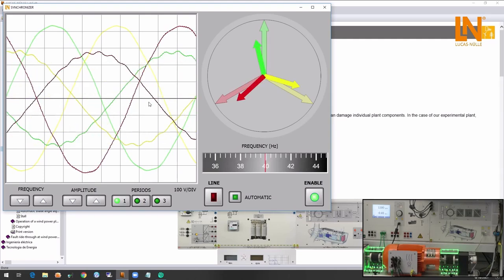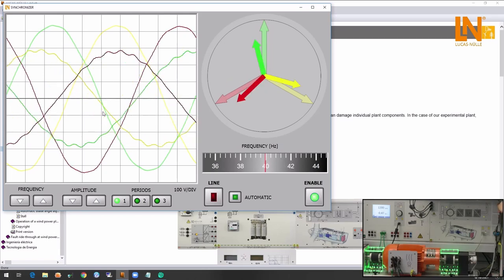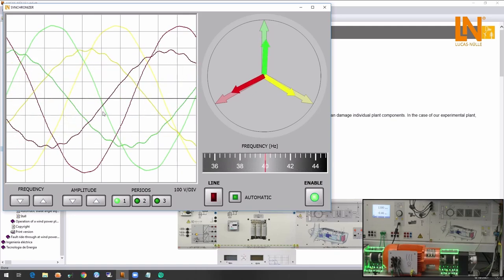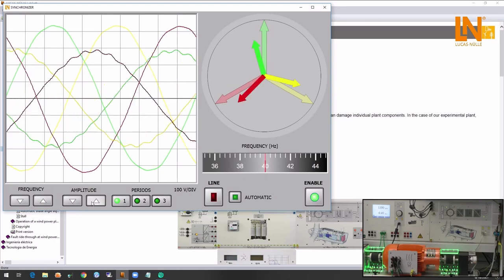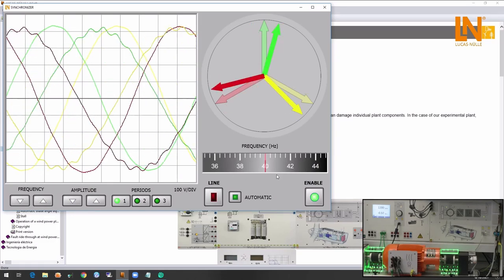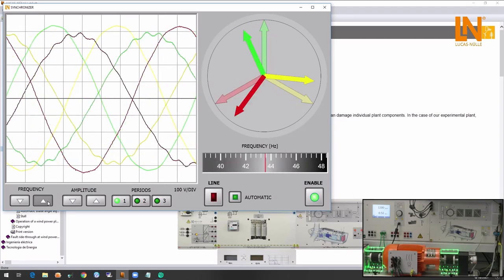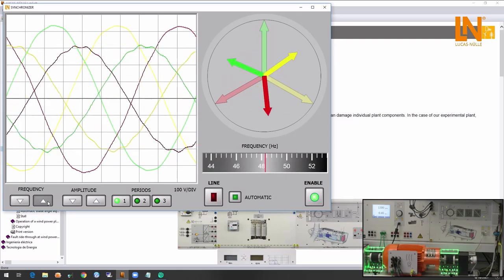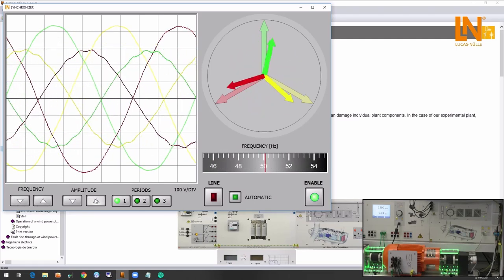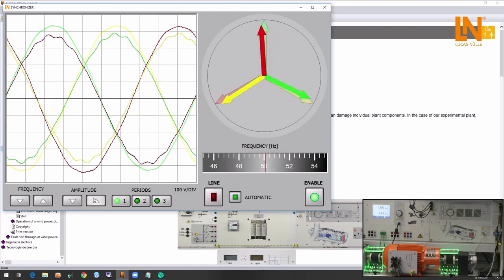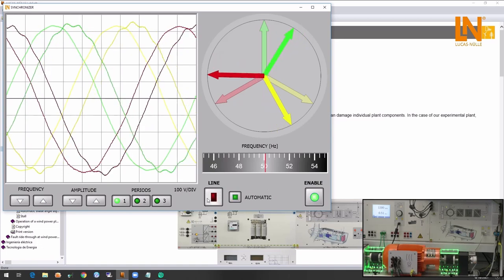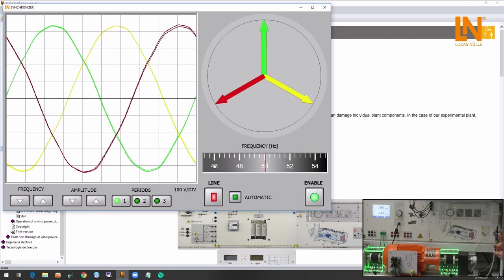I'm going to enable the software and then increase the amplitude. You can see that these are real measurements because if I for example remove one phase you will directly see it. Now I'm going to increase the frequency to grid frequency. Then I have to increase the amplitude again. And now we will wait for the right time to synchronize. Of course this operation can also be done in real power plants automatically.